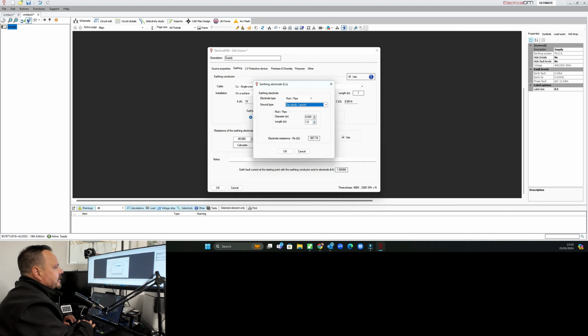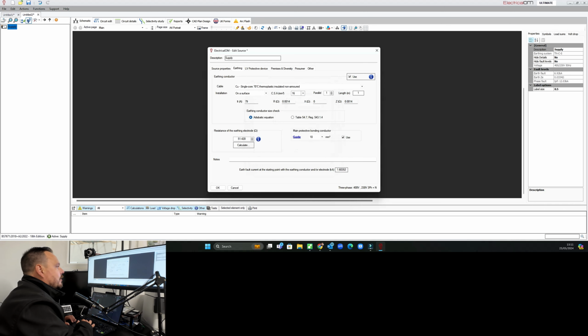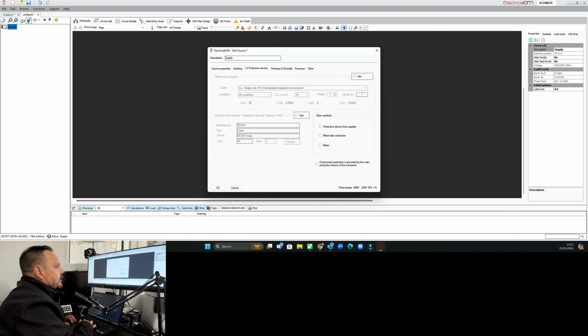So if you've got dry sandy gravel, you'd expect an earth electrode resistance of 800 ohms based on this particular type of rod. So if we say we've got a 4 meter rod and we're in, we'll say sandy clay, we'd expect 50 ohms, which is a good value. So we can use that to help us calculate what to expect in terms of our electrode as well, which is super duper useful.